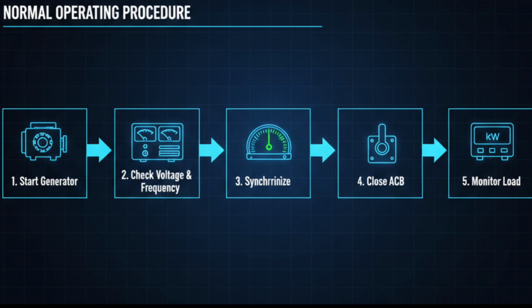If ship load increases, start another generator and share the load. Engineers must continuously monitor voltage, frequency, current, power factor, and generator temperature. Proper monitoring prevents overload and blackout situations.